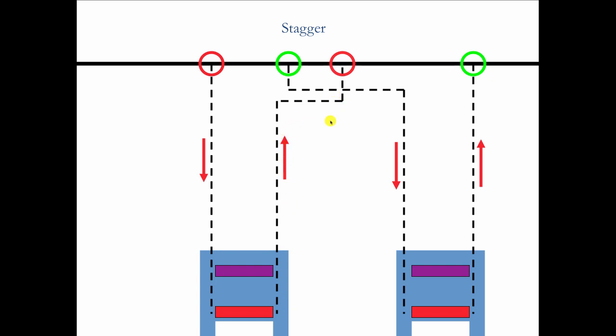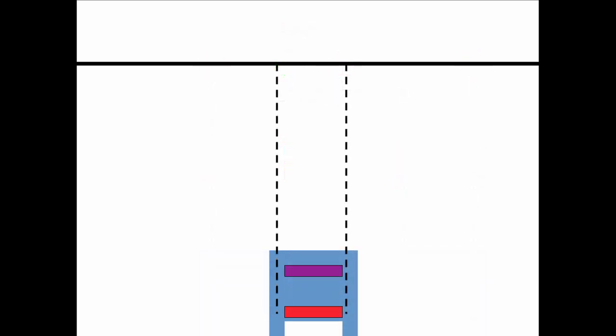If it's not heating, chances are there's no flow going to it. It's not air. So let's think about a builder back in those days building those houses in the 1950s. Direction of flow goes that way. You want it to go down to the radiator and come up, and let's say that's a 10,000 BTU radiator or convector. Now, 10,000 BTU is working with a 20 degree temperature drop. Well, that's equivalent to one gallon per minute. So we want one gallon per minute to go down and one gallon per minute to come up.